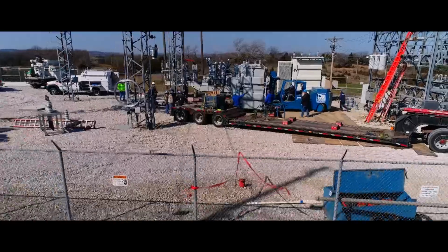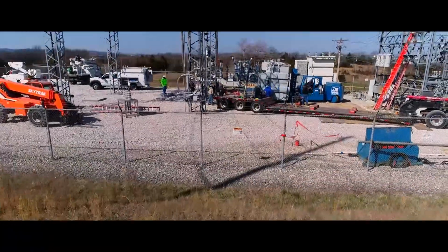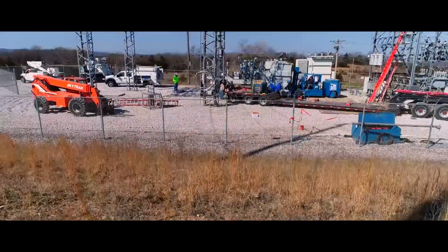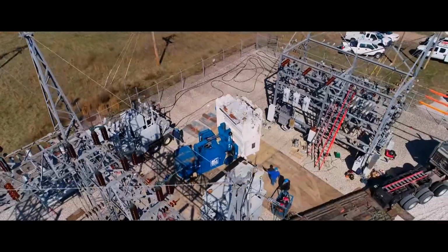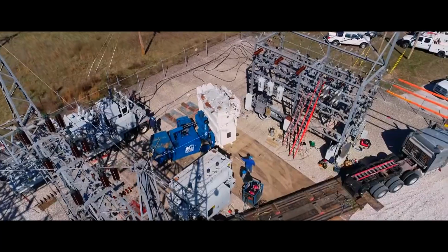There's a lot in addition to that preventative maintenance that goes into the preventative maintenance of our actual system. Once a month we check all of our special equipment, starting at the substation with a visual check - looking for animal damage, possibly lightning damage, bad arresters, and giving everything inside the substation a good visual inspection.